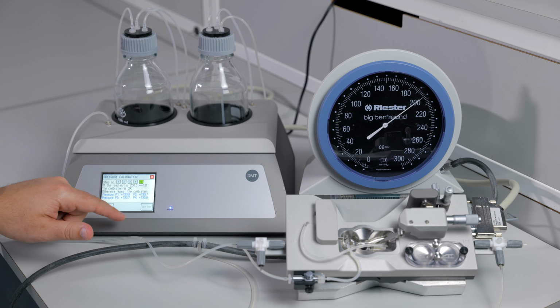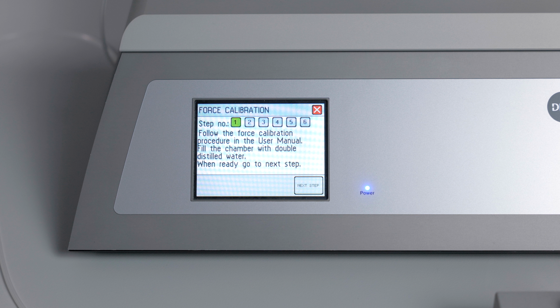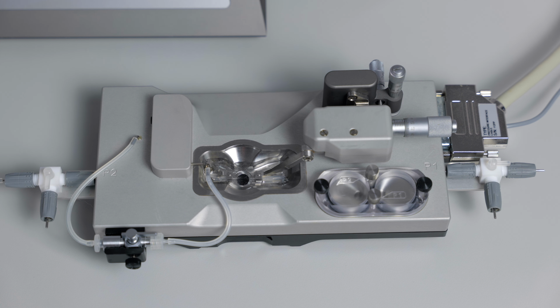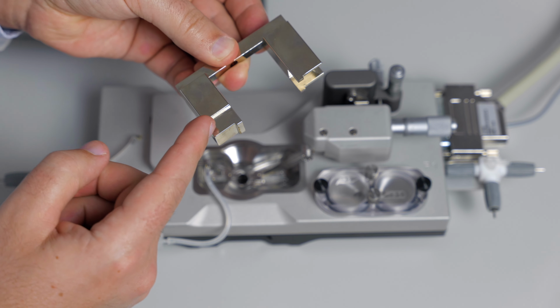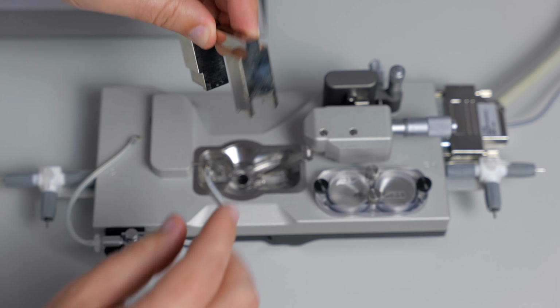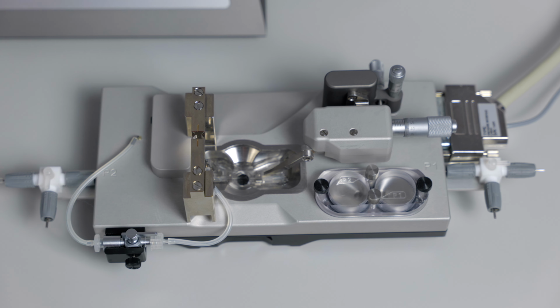In order to start the force calibration, you will need to access the force calibration menu on the touchscreen. Go to Settings and then Force Calibration. Again, Step 1 will ask you to follow the procedure in the manual. However, instructions will be provided on the touchscreen. Hit Next Step. Step 2 asks you to place the calibration bridge and T-balance on the chamber. You need to make sure that you are using the calibration bridge specifically for the pressure chambers. This bridge has a gap on one side and a cutout on the other. The cutout will ensure that the bridge goes over the force transducer housing, and the hollow section will go over the tubing if it's necessary.